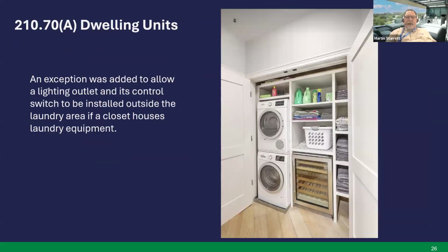So this has kind of been an issue because laundry areas are required a lighting outlet by our current code, and I believe 2020 as well. So whenever you look at this is a laundry area, but the problem was that if I put a light in that area, it's kind of covered up in the closet or there's no space. So now we've got an actual code that says, or an exception to a code that says, hey, you could bring that light outside of that area if it's a closet.